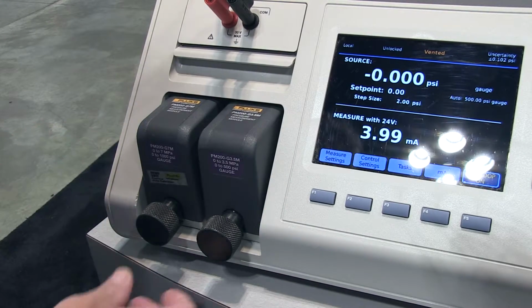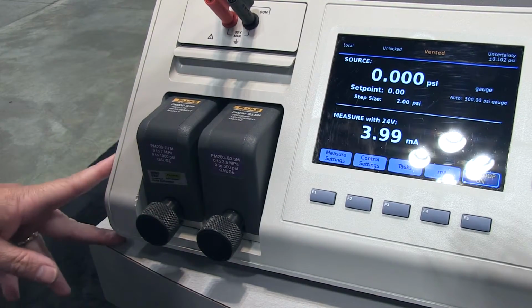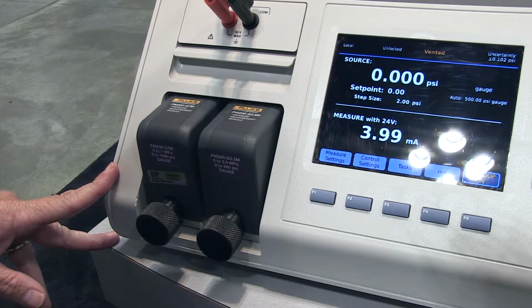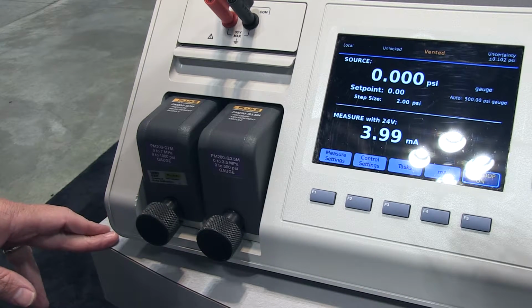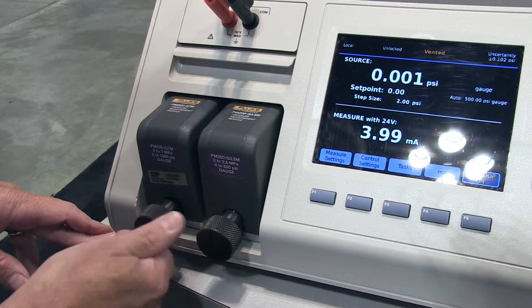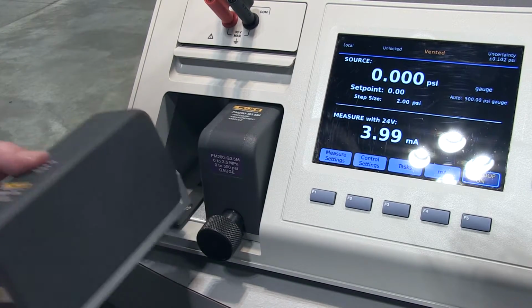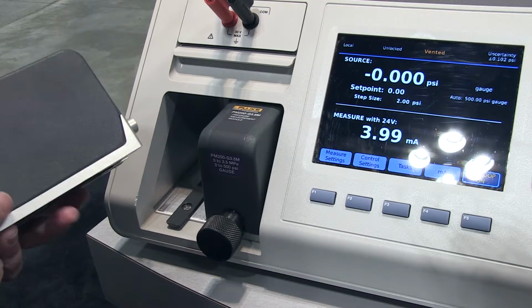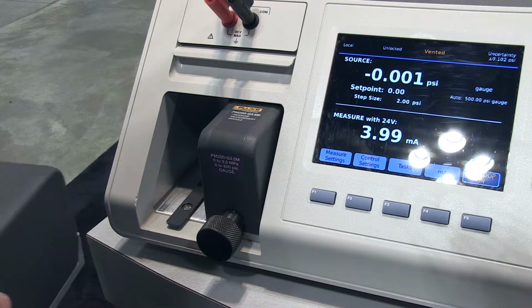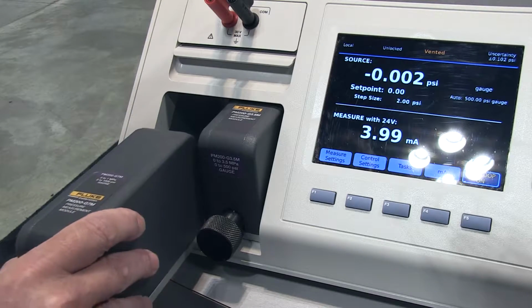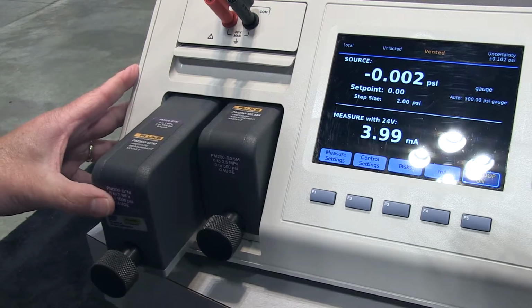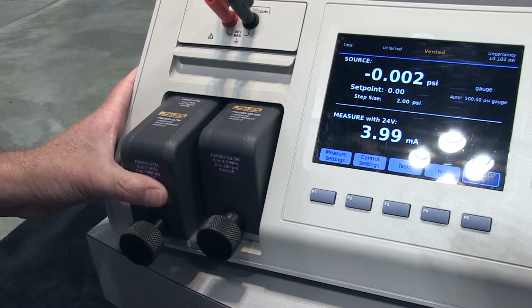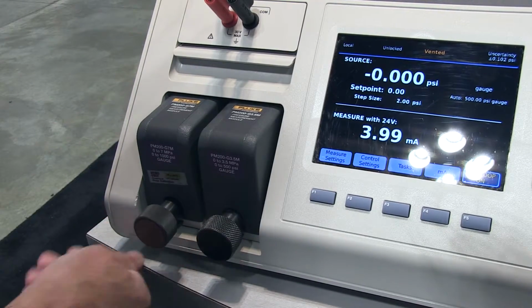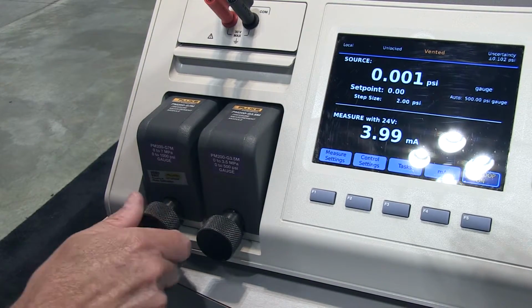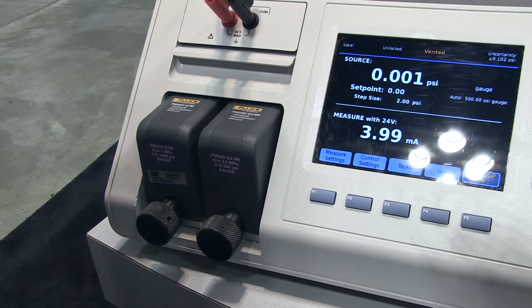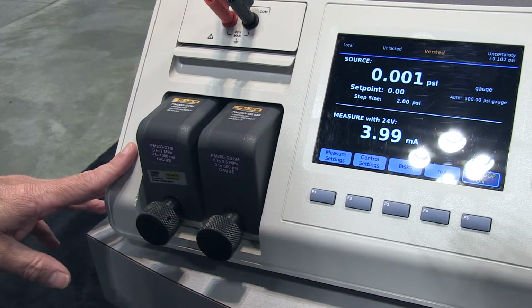So the 2271A uses these PM200 measurement modules, which were first released about 2 years ago with the 6270A pressure controller. They don't require any tools to remove from the chassis. These are independent and can be sent out for calibration. You could have spares on the shelf. You can have more than 2 modules, obviously, in your lab, but only 2 can be installed in the calibrator at one time. However, if you're calibrating things like analog gauges, 1%, 0.5% gauges, you may only need a few measurement modules to cover your entire range.